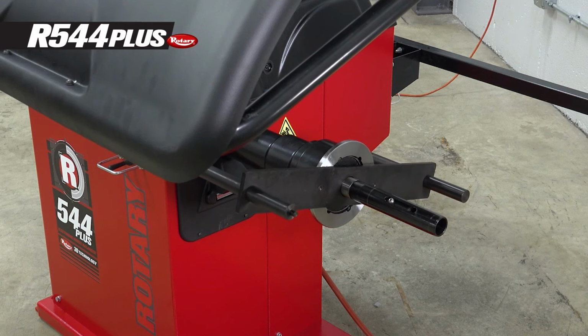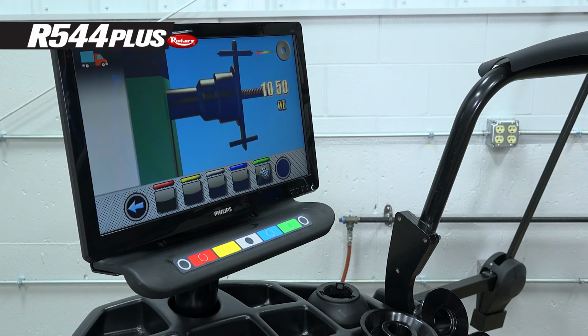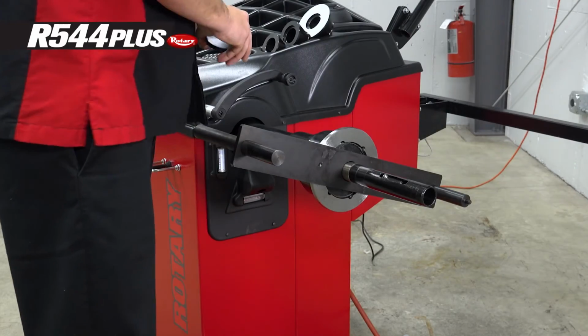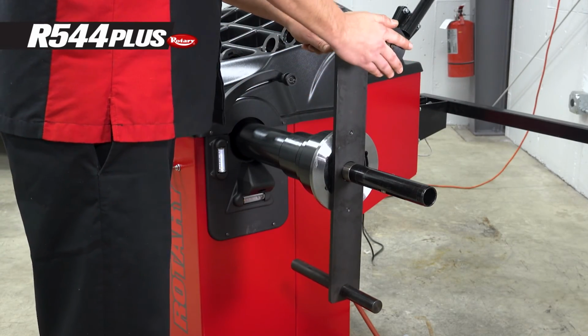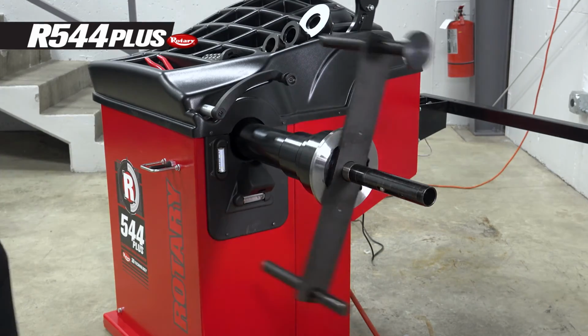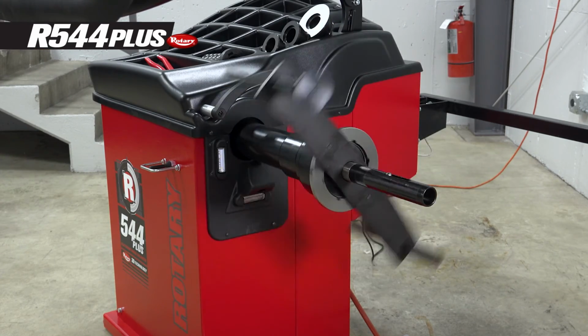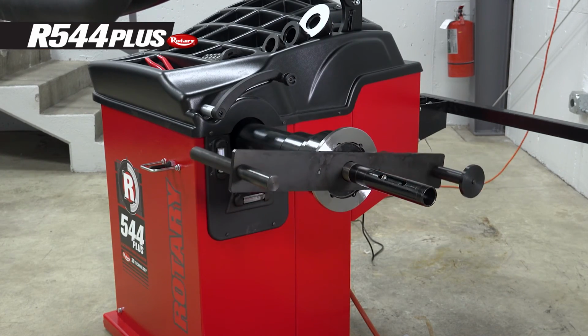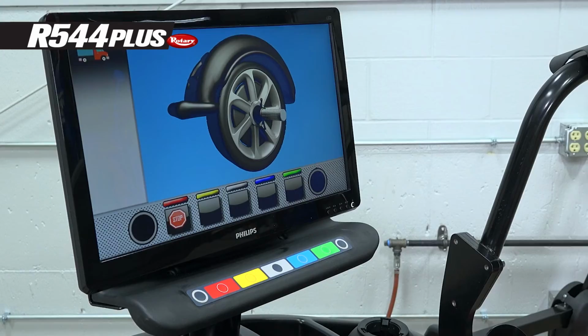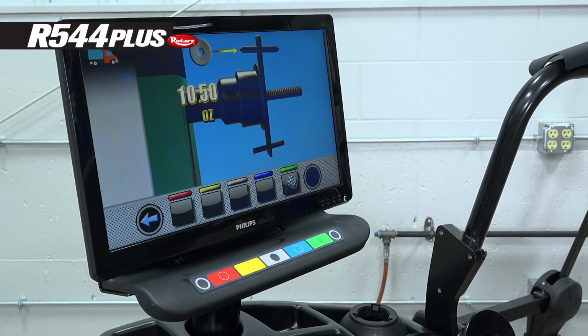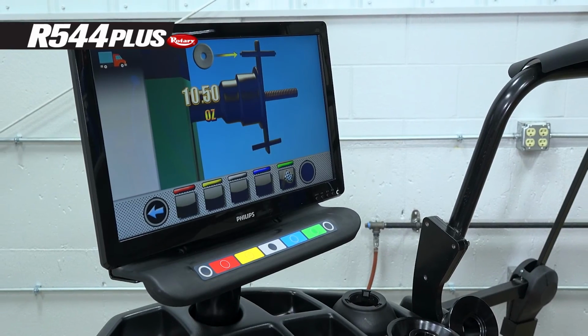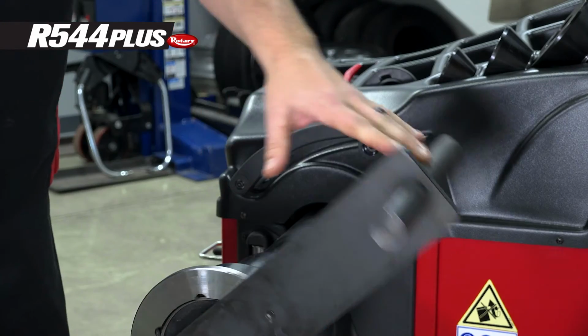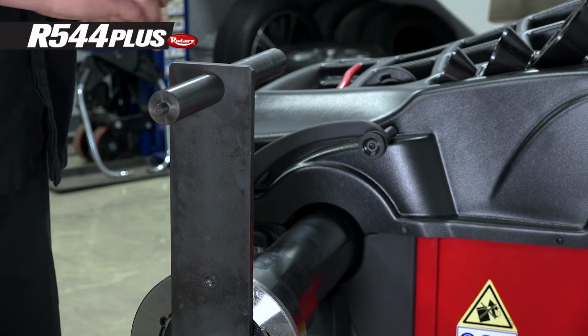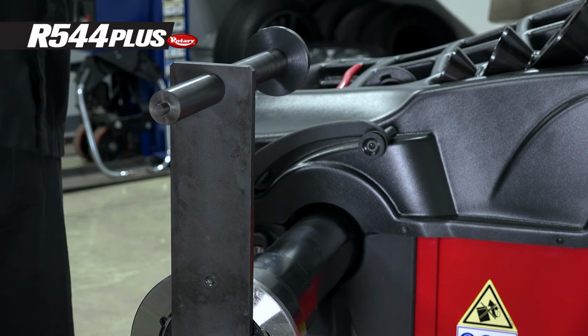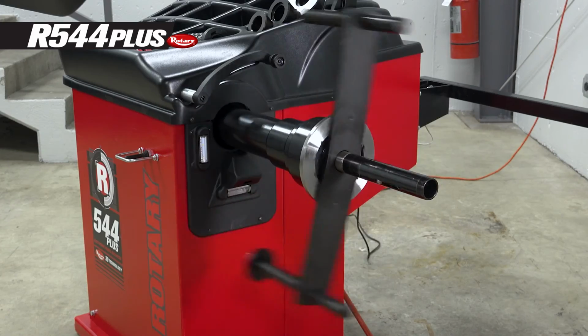When the shaft stops spinning, the screen will indicate where to place the weight on the jig. Raise the hood, rotate the fixture to apply the calibration weight at 12 o'clock, and lower the hood again. Once the shaft stops spinning again, the screen will indicate the next placement of the weight on the jig. Raise the hood, rotate the fixture to 12 o'clock, reposition the weight, and lower the hood for a third time.